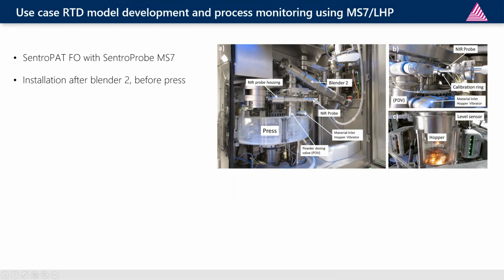In the probe there is also a calibration. The white reference is done by retracting the probe from the process automatically, placing it in the white reference position, taking a new white reference, and pulling it back into the process, which can be done as necessary - usually it's a matter of hours between those referencing steps.